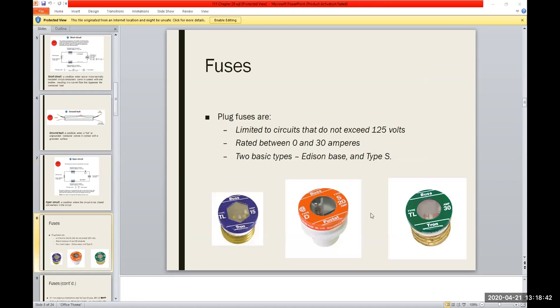Anyway, so there's what I was talking about earlier. These are the plug style fuses. Notice the screw size is different on each one, so it has a different diameter depending on the amp rating. Believe it or not, in some houses these are still existent. They haven't changed anything, and it's a grandfather clause, so if you don't have anything changed, it's still allowed to be. You can still buy these plug fuses. Different hardware stores still carry these. They're not as big of a demand as when I was a kid, but they're still out there.